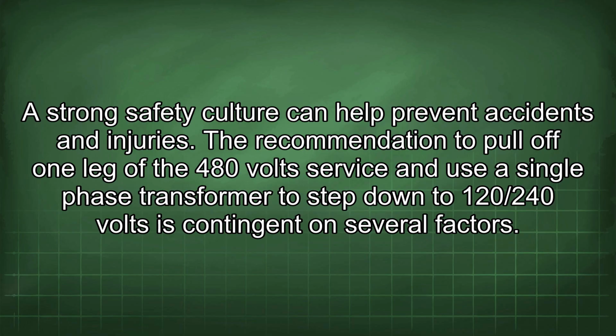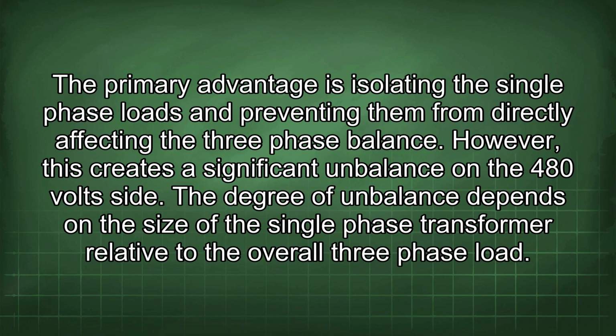The recommendation to pull off one leg of the 480-volt service and use a single-phase transformer to step down to 120/240 volts is contingent on several factors. The primary advantage is isolating the single-phase loads and preventing them from directly affecting the three-phase balance. However, this creates a significant unbalance on the 480-volt side. The degree of unbalance depends on the size of the single-phase transformer relative to the overall three-phase load.